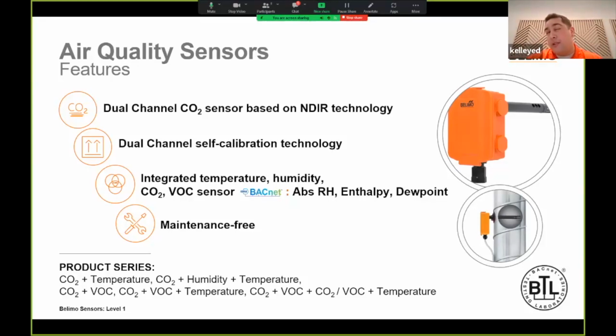In the field, if you look at competitors' offerings and so on, a lot of them will have both options. One option is typically called semi-occupancy or semi-occupied, and the other product is for full 100% occupancy. So the full occupancy technology is this NDIR technology. Really, long story short, we have an infrared sensing element within our device itself. It sends out an infrared beam and is received by a filter. Depending on the amount of CO2 in the air, that beam kind of loses strength.